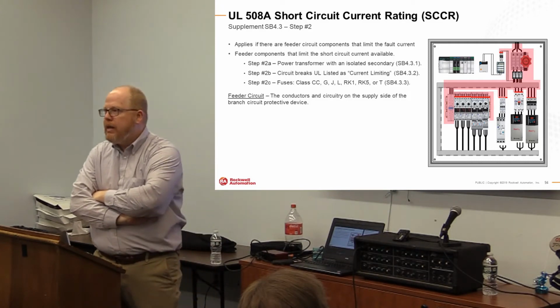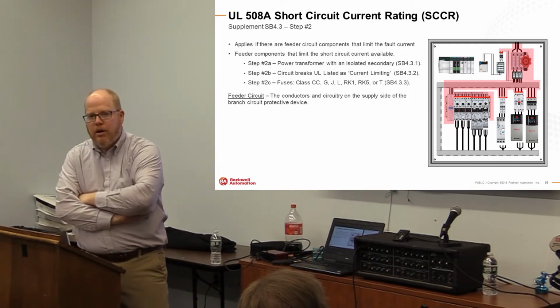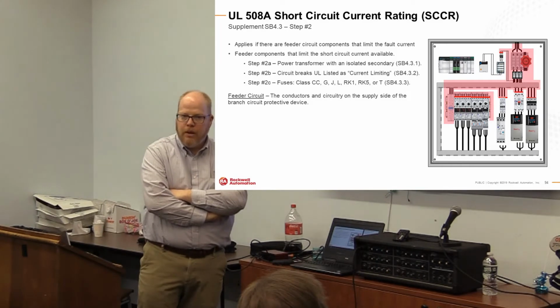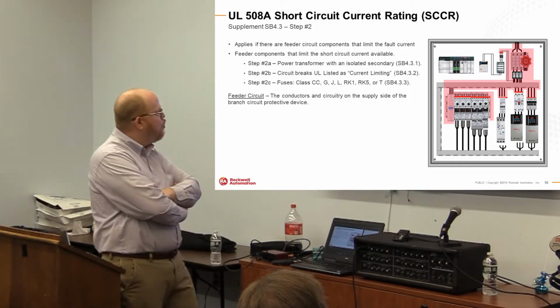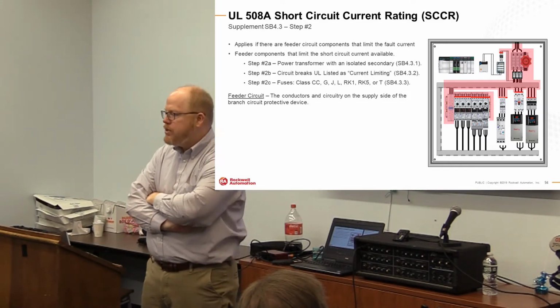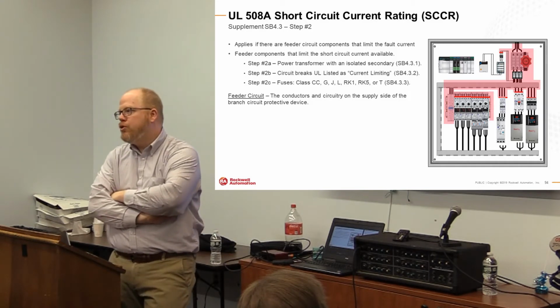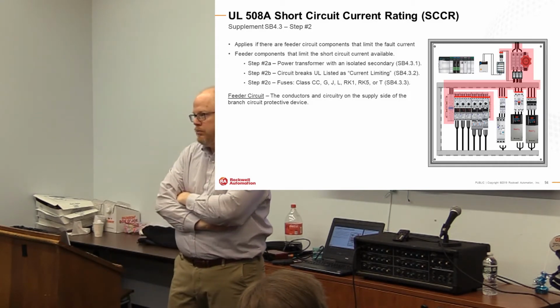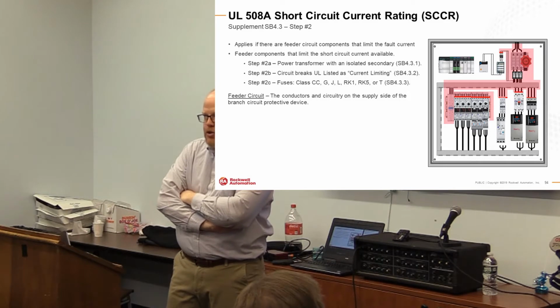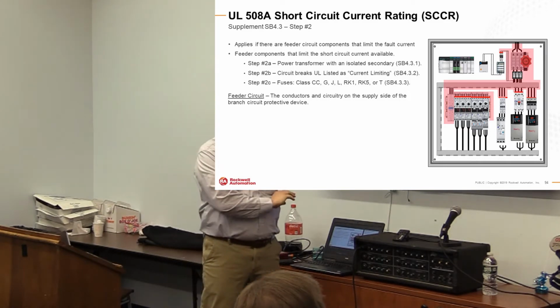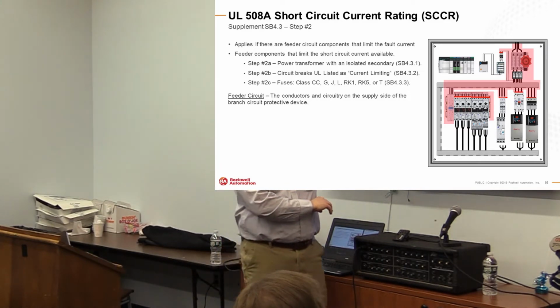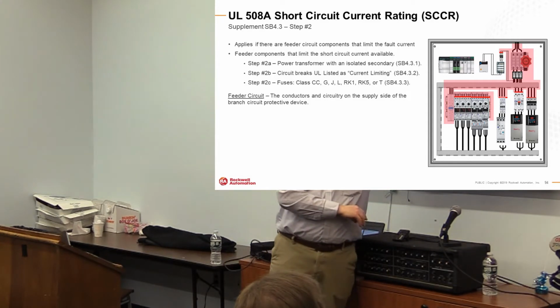So let's talk about step 2 when it comes to this idea of current limiting. What I have highlighted here is the feeder of a power circuit. And again, when we try to leverage current limiting rules, it's important to keep in mind that we're doing this in the feeder for the various downstream branches. So what's highlighted in red or pink here is the feeder. These individual loads are branches.